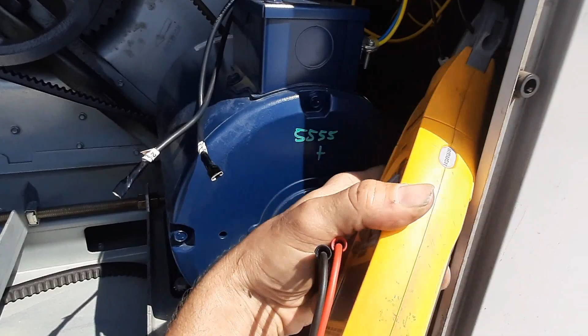All right, we got that pulled. Cross your fingers. I hooked up the bottom again, and I hooked my transformer back up. Nothing's connected over there. Let's see if I get longer than 2 seconds. Listen closely. I'll bet that relay was trying to energize and there's something wrong on the other side. Still got power. It's showing me status. So good there. Let's see. Go ahead and check my fan motors like I was going to.